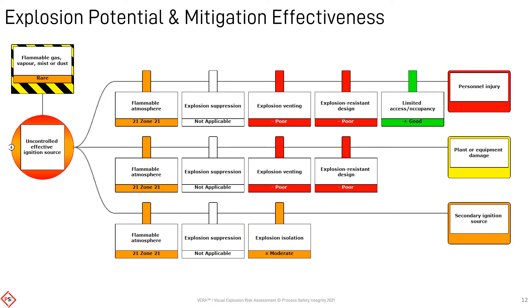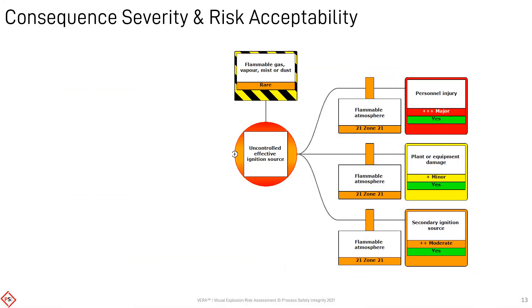The effectiveness of the mitigation measures are also relatively ranked in the same way as the prevention controls. The relative severity of the effects on personnel or the assets can be used to determine the risk target. The combination of threat frequency, prevention effectiveness, flammable atmosphere potential, mitigation effectiveness, and consequent severity can be used to qualitatively or, with good data, quantitatively predict the residual risk, which is compared to the risk target to determine if the risk is acceptable or not.